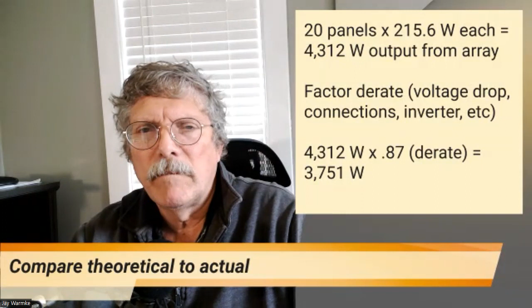So you go to the inverter output. If it's producing somewhere near there, because of course conditions are going to change a little bit by the time you run back and look at these things, but if it is producing that, then your system is producing as designed. If it's not, well, now you got to do some troubleshooting. If it's only producing 2,000 watts, something's wrong. Maybe one of the breakers in one of the strings is disconnected, or a wire is loose, or something like that. So that's what you got to do.